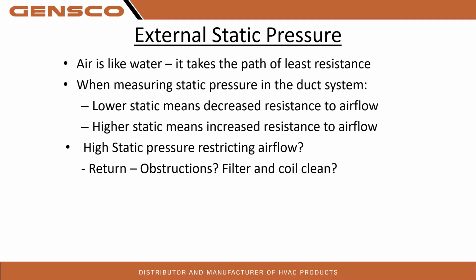I just had one recently, again, new construction, where the contractor was running the system during the sheetrock phase. That sheetrock dust coats that evaporator coil, and as soon as we run it in AC and introduce moisture into that sheetrock dust, oh, it creates a concrete. So if you guys are doing new construction, be aware. I put it in my estimates that if they ran it during construction phase to preheat the house, they were responsible for me cleaning it and responsible for repairs, because you will burn up the blower motors. You'll lose efficiency. They're just doing the homeowner that purchased that home a great disservice to run that. And there's no way around it sometimes.